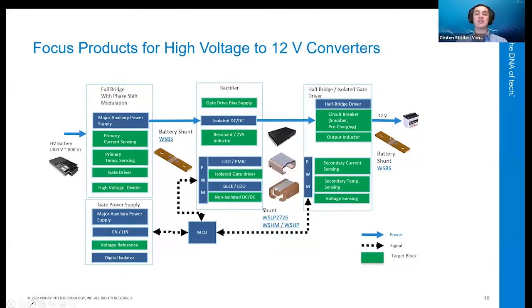You can get better sensing accuracy out of the 4-terminal devices, as we've discussed, but it will obviously depend on the design that the customer ultimately wants. The advantage of the WSHM is that we can get high power resistance values, so if the customer is looking for a system that requires 100 milliohm, the WSHM is the route to take. If they need 5 milliohm or less, the other resistors will be able to fit the bill.